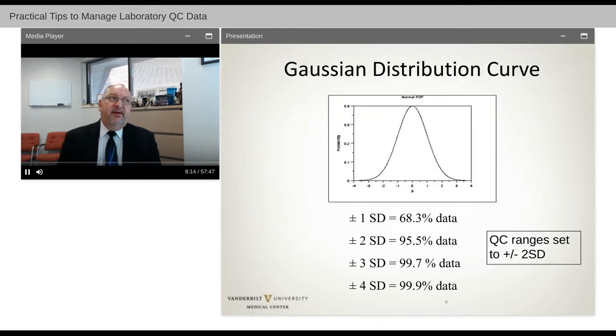If we randomly analyze a specimen repeatedly over time, all of those results should scatter around a mean and within two standard deviations of that mean form a bell-shaped curve. In other words, 95% of the data under this bell shape, or Gaussian distribution, should fall within two standard deviations of the mean. Three standard deviations is about 99.7% of the data. So most of our quality control ranges are set up to plus or minus 2SD, as is our reference intervals and other aspects of what we do in the laboratory. We use the two standard deviation ranges in quality control for setting up and estimating future performance.